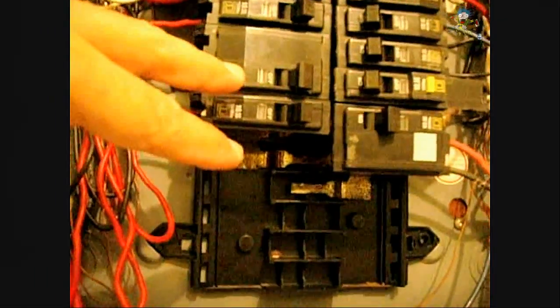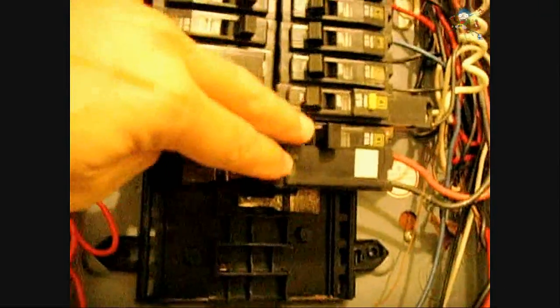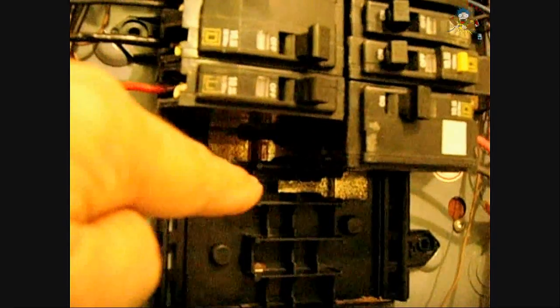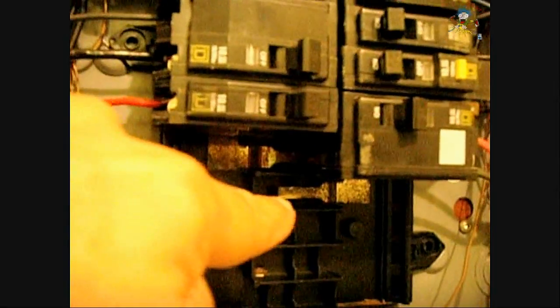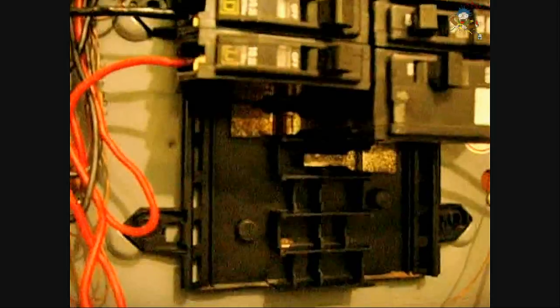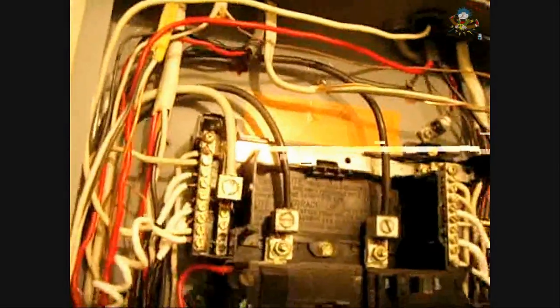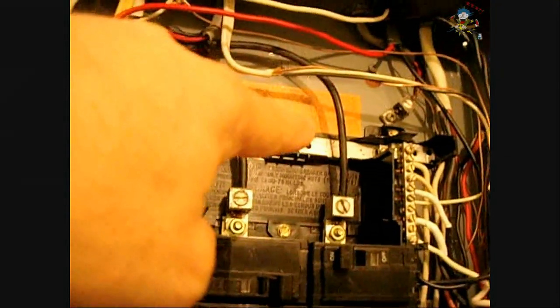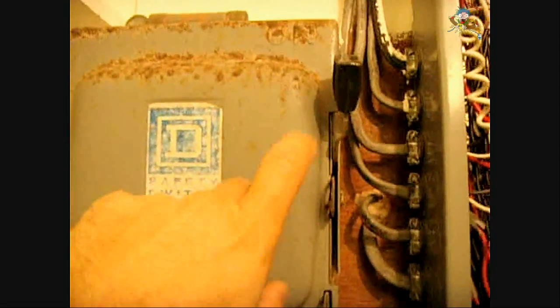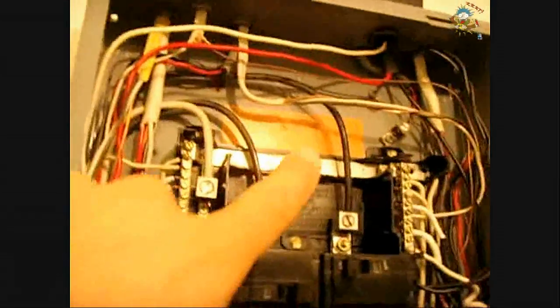So when you want to have 240 volts applied to a circuit, you have to make sure the circuit breaker is clipped into each lug. So you're going to want to look at that connection right there. And a lot of the time I have seen in the past that when this clip here is burned or pitted, you're going to see the same thing on the bus bar. After disconnecting the main power, this panel here does not have the main breaker inside the enclosure. It's separate. It's located over here as a throw switch. Yours might be in a separate housing like this, or it may be at the top.